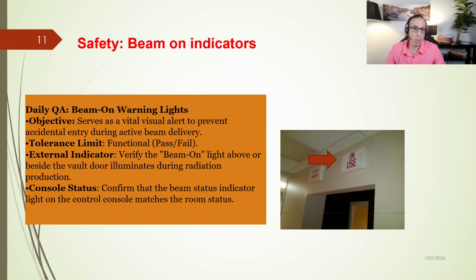To test these indicators during your morning QA, you will look for specific things while the beam is firing. First, look at the external light mounted right above or next to the vault door, the bunker door. That means it must light up brightly. Then check your control console to ensure its built-in status indicator matches the room lights perfectly. Always keep in mind that if any of these bulb filaments burn out or the warning circuit fails, the machine is legally down. You cannot treat patients until engineering replaces the indicator, because an invisible hazard must always have a functional visual warning.